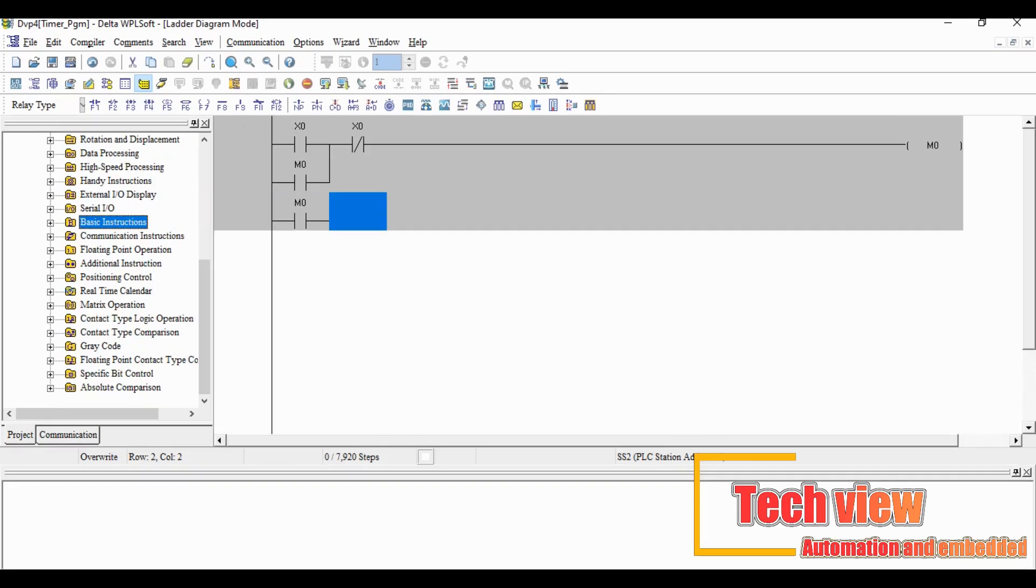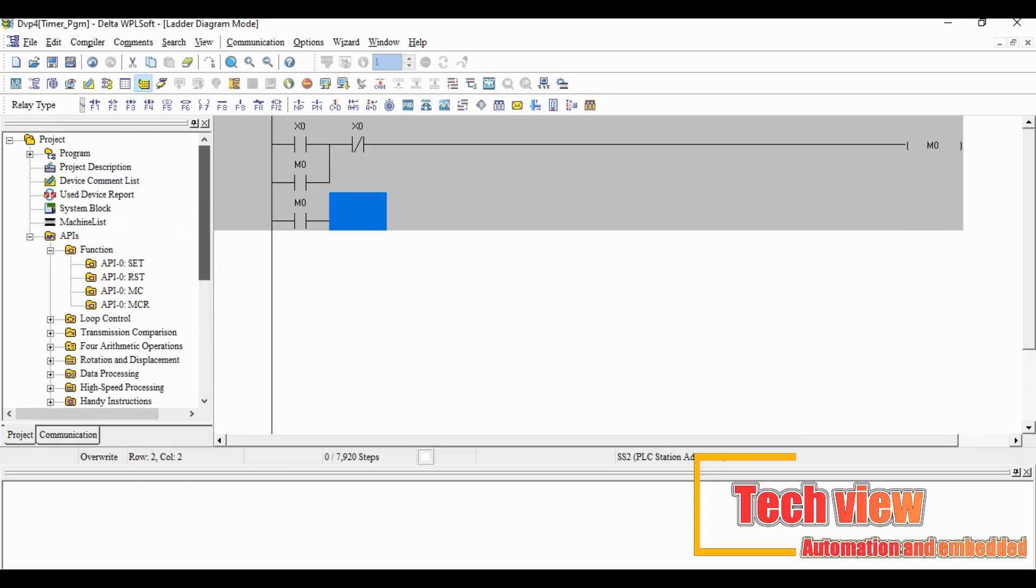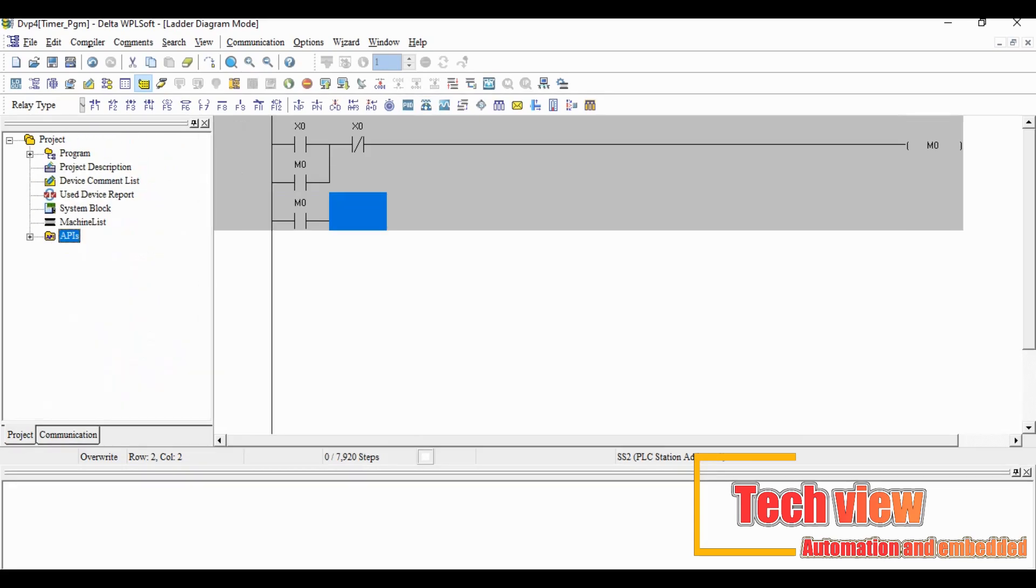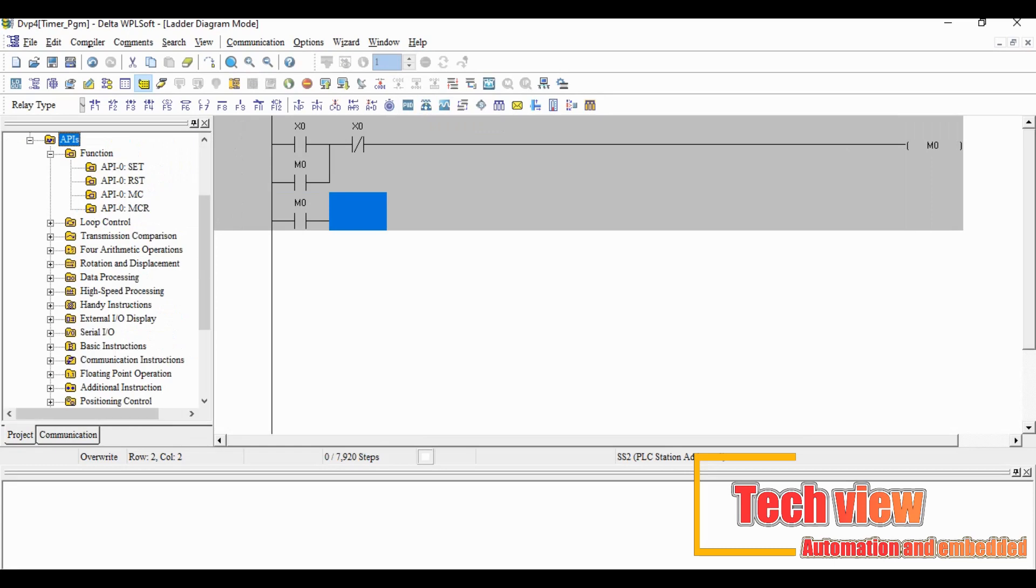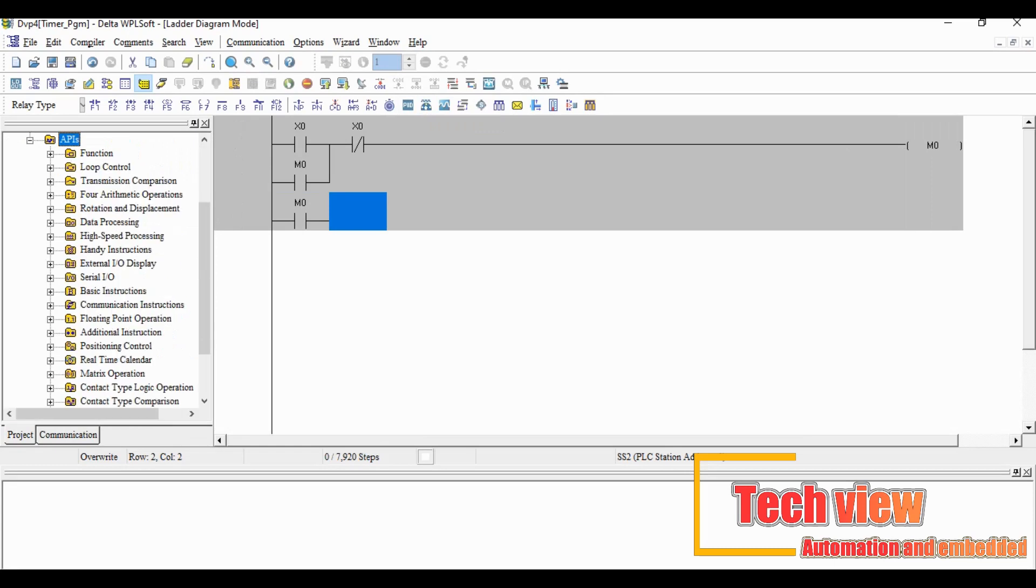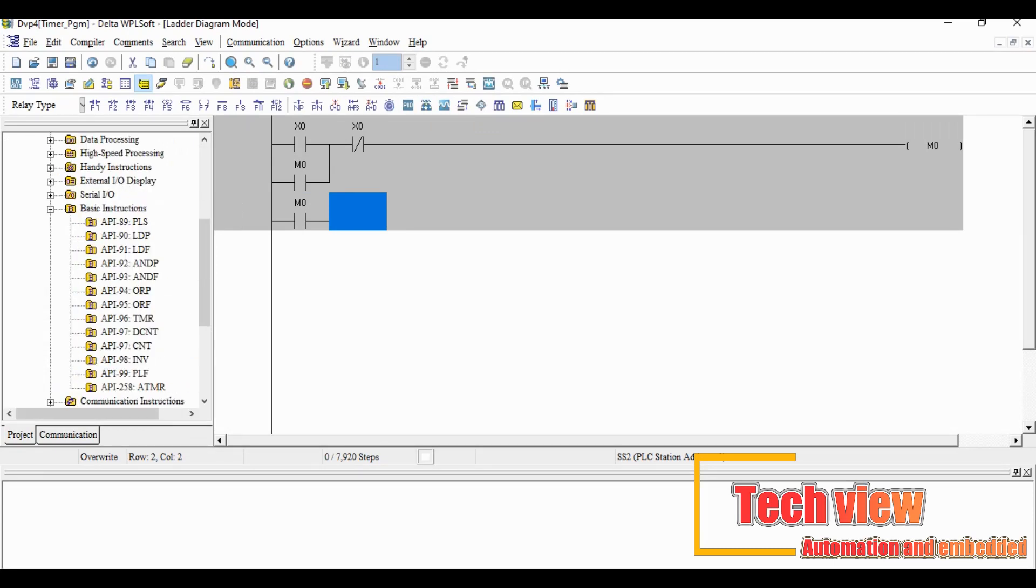Now we are going to use the timer function before that we insert the new row and add M0 as input. After add M0, we have to insert timer instruction from the API list which is located in the left side menu. From that open the basic instruction and double click API 96 TMR.